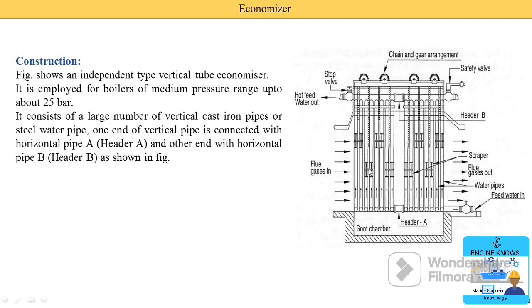There are a number of scrapers installed. These scrapers are used to remove the soot deposits. To operate the scrapers up and down, a chain and gear arrangement is provided. Due to this chain and gear arrangement, the scrapers move up and down, and the soot that sticks on the pipes is collected in the lower part, known as the soot chamber. The flue gases enter from one side and exit from the other side.